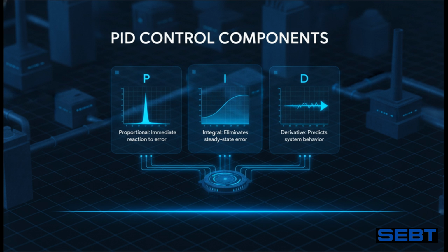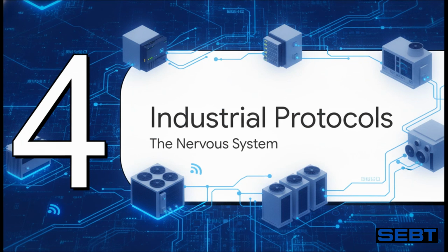And D stands for derivative. It looks at the rate of change, to essentially predict the future. If the temperature is dropping really fast, the D will actually start pulling back on the cooling early so we don't overshoot our target. Working all together, they handle stuff like a sudden massive increase in room occupancy flawlessly, totally avoiding any overreaction. Okay, moving on to Section 4, Industrial Protocols.